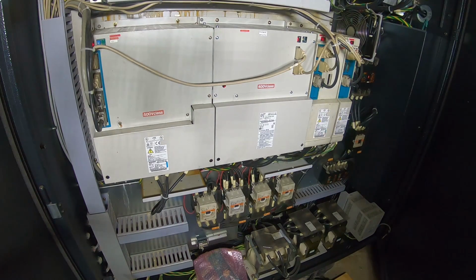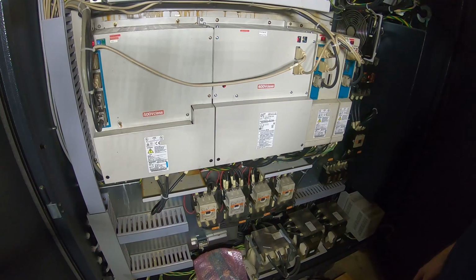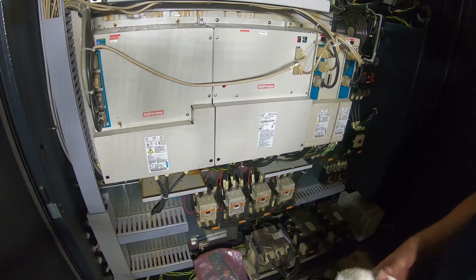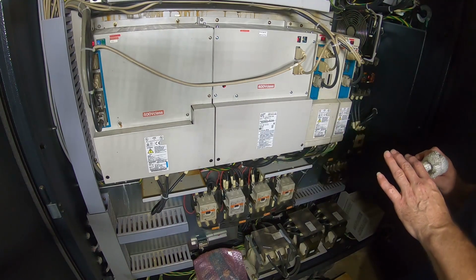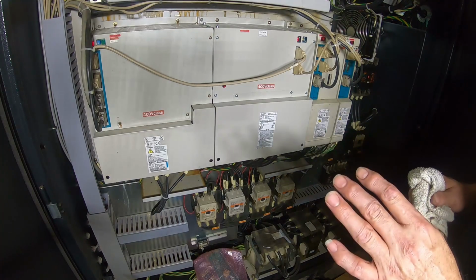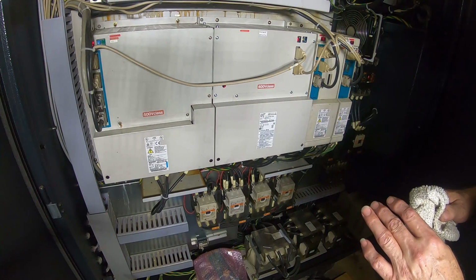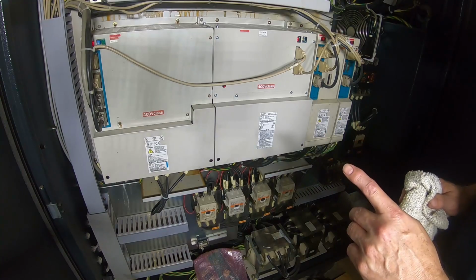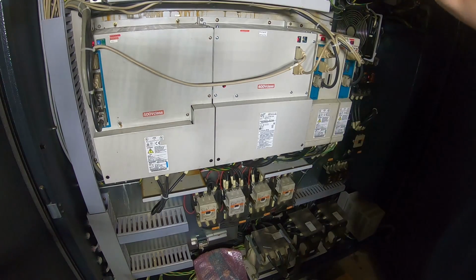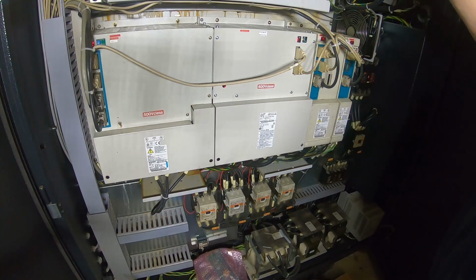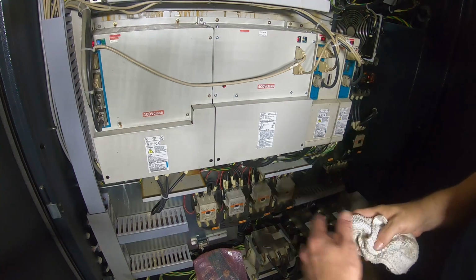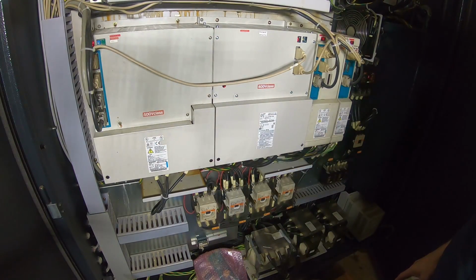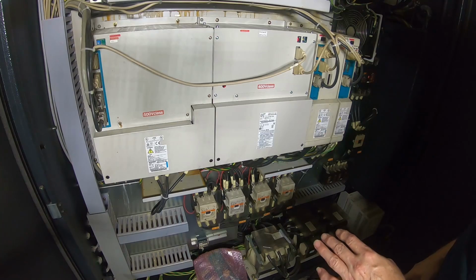Let me go around and turn the control on. So far so good. The control has to boot up before the servo power pulls in. I've released emergency stop back there already on the control, and all these drives are so far reading the same LED reading, which is good. This came up with a 76 on it, which was the alarm 76 before.